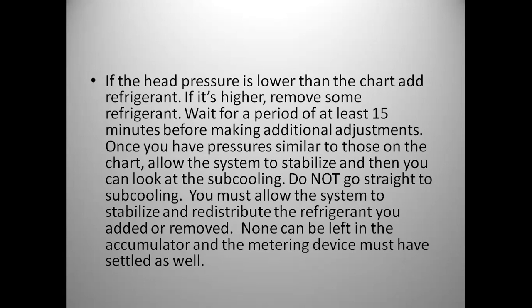If the head pressure is much lower than the chart, you'll want to add refrigerant. If it's higher, you want to remove some refrigerant. So that kind of plays into a downflow or a horizontal right unit with a very short line set. You'll come right out of the gate overcharged, especially in heating. It'll be almost immediate. So if you notice your head pressure, discharge pressure is skyrocketing way early, start recovering some refrigerant to get that to a stable level.